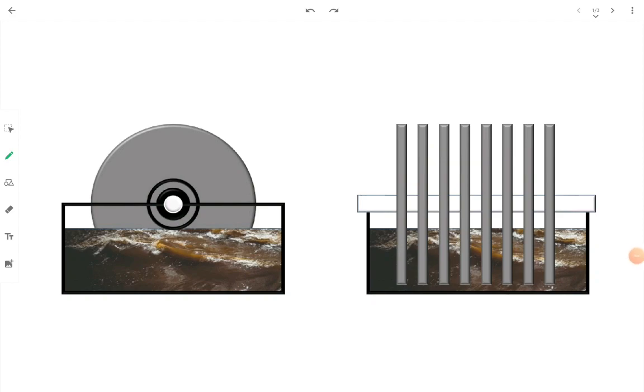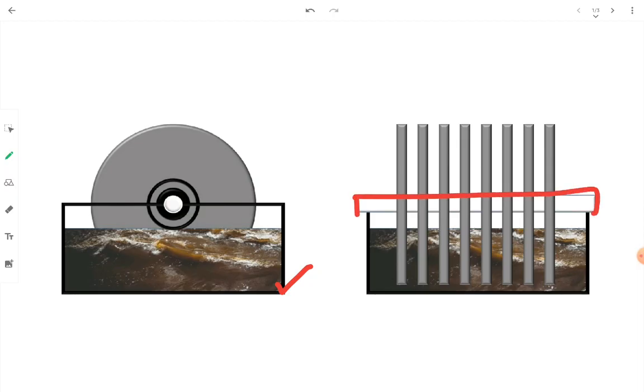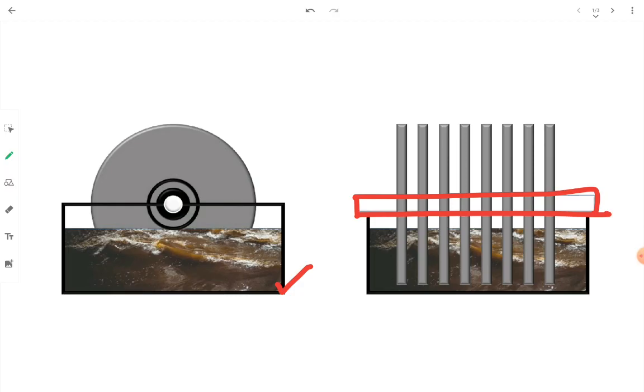Rotating biological contactors or RBC is a biological treatment unit with attach growth process. In RBC there is a tank which is filled up with wastewater and a shaft is fitted over the tank which holds number of closely spaced thin circular disc and this shaft rotates at the rate of 1 to 2 rpm.